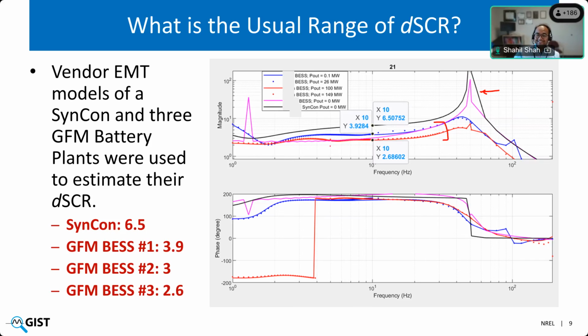As you can see, all of these resources have a more or less constant gain within this 4 to 40 hertz frequency range, which is where we have selected to check the grid forming behavior. Because in steady state, even grid following controls can provide this voltage source behind reactor type of response. When we talk about grid forming, we are really interested in the fast timescale behavior in the transient to subtransient timescales. That roughly translates to 4 to 40 hertz, basically from a few tens of milliseconds to a couple hundred milliseconds type of response.